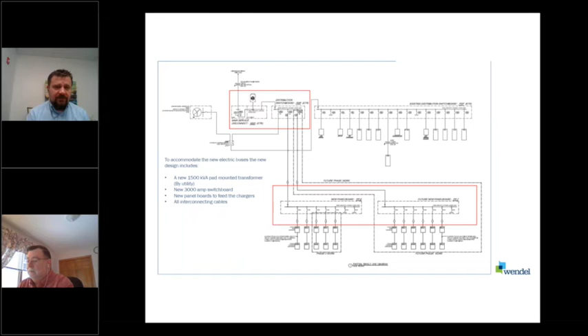So we settled on 125 kW chargers, and the reason for that is we knew that they would charge a bus in about 4 hours versus a 60 kW. So that gave us the flexibility to fully accommodate 11 buses within an 8-hour charging period. So we were going to stagger them, charge 6 and 5, one group after the other. Larger chargers take up more space, and after reviewing a few options for locating the chargers, it was determined that the best would be to locate them outside and have the remote charging dispensers on the inside closer to the vehicle.